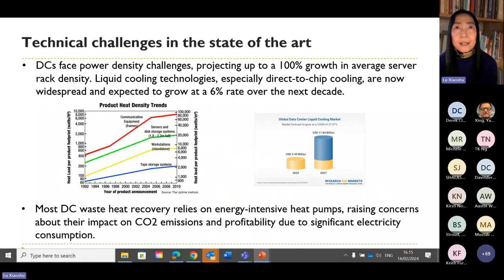So despite the applications, technical challenges exist. First, the data center's energy density grows dramatically, up to 100% growth in average server rack, as shown in the left graph. Therefore, liquid cooling, especially direct-to-chip cooling, is expanding now with a very high growth rate also, as shown in the right-hand side graph. Second, most data center waste heat recovery methods depend on heat pumps that consume significant electricity and are also very costly.